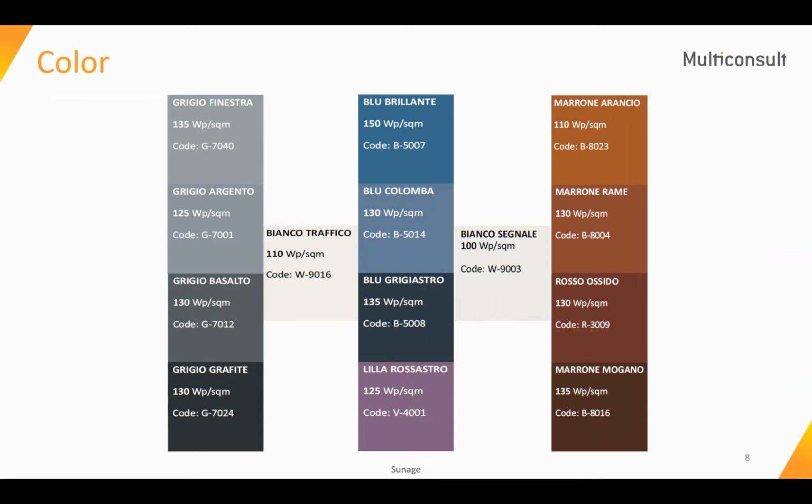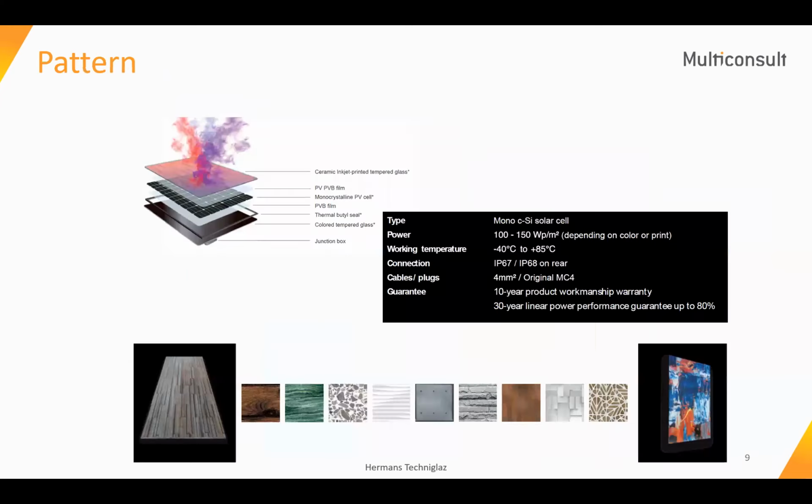So here we see different colors from one manufacturer. The best efficiency that we could expect is with dark blue and black colors. The efficiency, as we say, is 20% or something like that. And when we go toward whitish, reddish colors, the efficiency goes down to 10%, 11%. So with different colors, we can expect this range of 11, 12% to 20% for crystalline silicon.